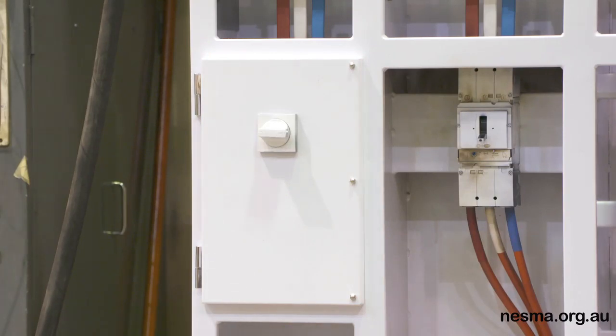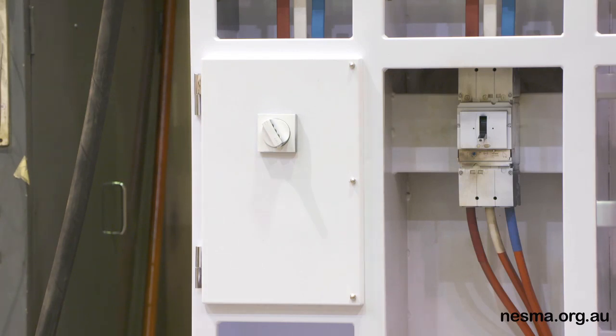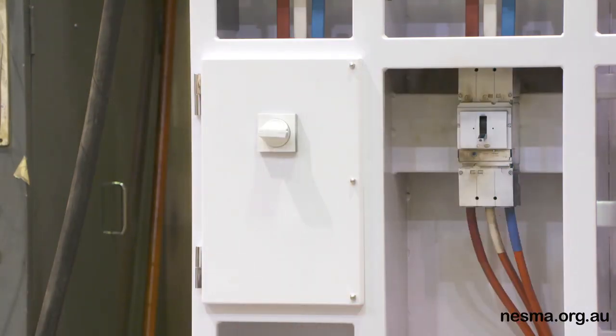So we're just seeing the test run through there. You're seeing, because there's no real seal, the doors, if you want to call it, burping a little bit, and we're just seeing a little bit of bowing of the door, and we may just get a little bit of the gas release from around the top edge seals. There is also a small vent inside that compartment, and you can see at the very lower edge of the unit under test, some arc products escaping from that functional unit just at the base of the unit.